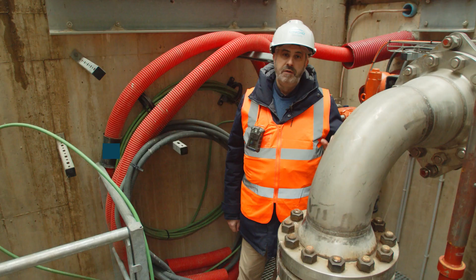This is the production well. Geothermal water is chemically dangerous. It contains salt and particles of matter, and it's very corrosive. To avoid corrosion, a corrosion inhibitor is injected at the bottom of the well through this pipe. Also, to extract geothermal water, a submersible pump is used—an electrical pump located in the pumping chamber about 250 meters deep.